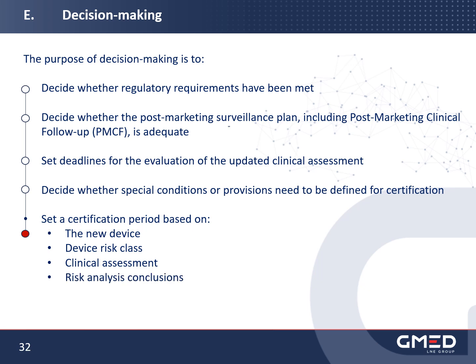set a certification duration, i.e. the period of validity of the certificate based on the number of parameters, including the new device, device risk class, manufacturer's clinical evaluation, risk analysis conclusions. The certification period defined by the notified body may in no case exceed 5 years.